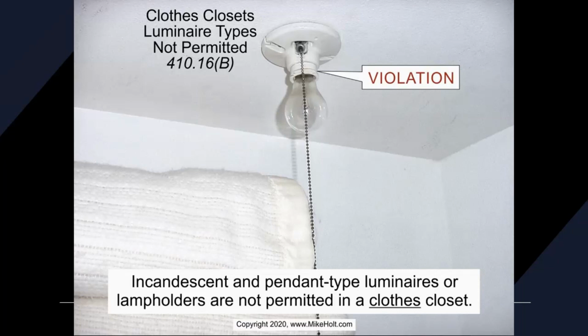Clothes closet luminaires. We can't use this keyless. This keyless light is a violation. Incandescent and pendant type luminaires are not permitted in clothes closets. Doesn't take a lot of thought to see what would happen if that hot light bulb burst on that, what I'm assuming is a cotton blanket right there. It's a great example.